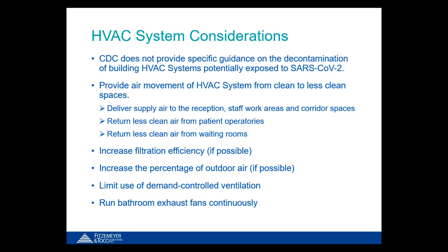They recommend increasing the amount of outdoor air to the HVAC system if possible. In the case of this dental practice, there are two small residential style systems, and neither system has any outdoor air being delivered to it today. So they simply rely on operable windows to meet the ventilation code. We considered, as part of that project, adding some ductwork and exterior louvers to bring in some outdoor air. However, we found out through calculations that the system could only handle a small amount of outdoor air, and the cost to install all of that was so high that it just didn't make a lot of sense to go down that road. There were other options that we recommended instead, which we feel can provide more bang for the buck.